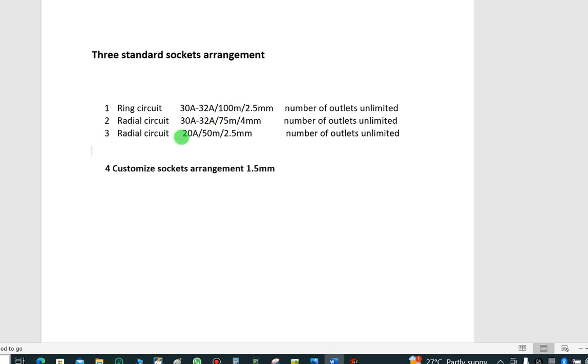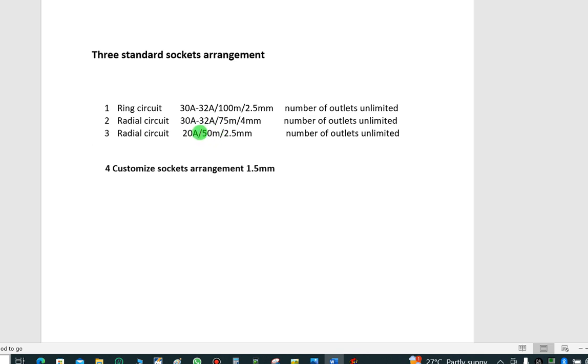The third arrangement is another radial circuit. This one does not return to the board — it's radial, not a ring. The protective device is 20 amps, the length of run is 50 meters, and the cable size is 2.5mm². The number of circuits is still unlimited, but the constraint of 50 meters applies. Make sure your circuit does not exceed 50 meters. That is your limitation here.